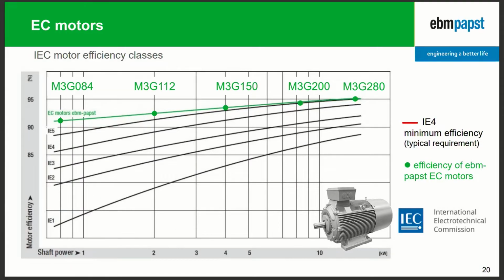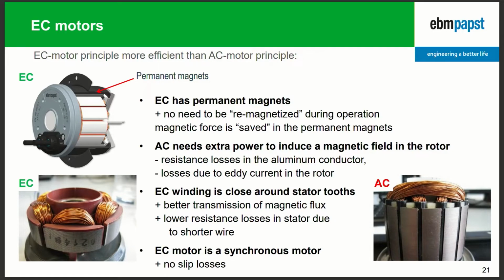Comparing our EC motors with AC motors, this happens quite often. There is an international efficiency grade, which is not suitable for EC motors because EC motors are out of the scope. But anyway, we get compared in projects with these levels, and we can say that we are far above IE4 level. Especially on the lower power side, we are above the IE5 levels, which are not yet in place, but their figures are available. So EC fans or EC motors, EC is a technology, electronically commutated motors, synchronous motors, permanent magnet motors, is all naming the same thing.